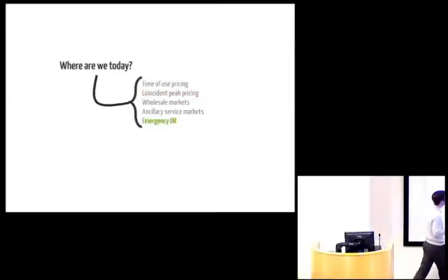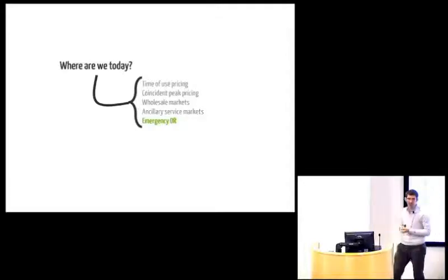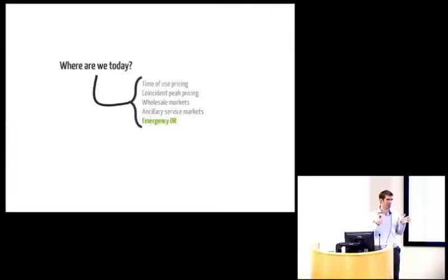The closest to a win-win that exists today is emergency demand response, where the data centers sign up at the beginning of the year and say, okay, I'm willing to provide up to X response once or twice a year when you ask for it, and I'll pay a big penalty if, when you ask for it, I can't provide that response. So you opt into this at the beginning of the year. You get paid just for being in the program. Most years you don't get called. If you do get called, you have to do something, otherwise there's a huge penalty.